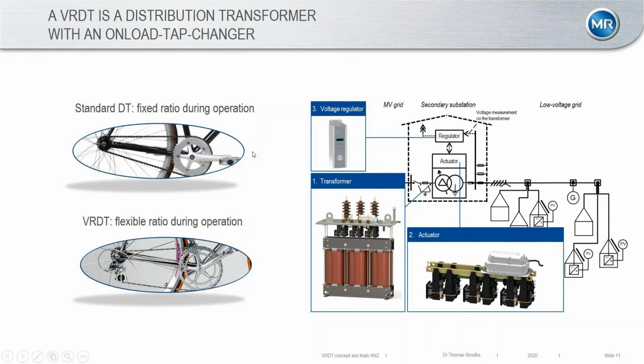This is what MR has manufactured for 100 years, so we have a lot of experience with that. You need just a standard transformer, maybe a little bit more space on top of the core, and then another voltage regulator relay that can be connected, which does the voltage measurement, and then triggers the tap changer to move in the right direction to suit the voltage needs in this particular substation or along the feeders.